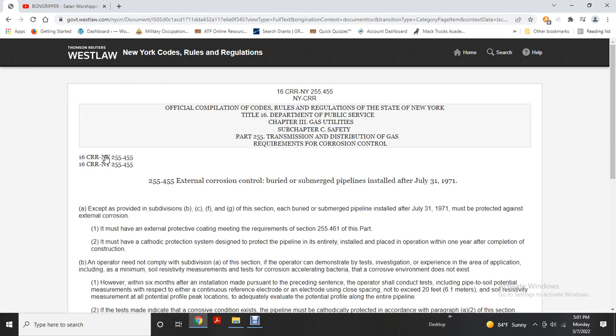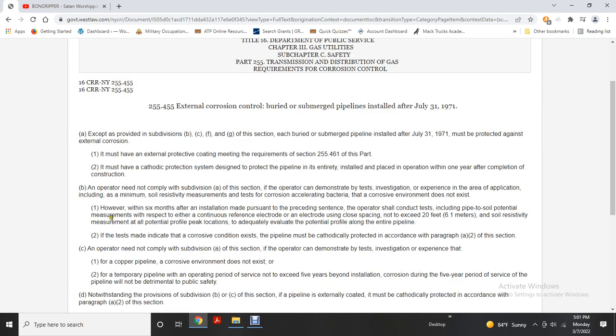External corrosion for buried and submerged pipelines installed after July 31st must comply with subsections B and C. Cathodic protection must be designed to protect the pipeline, with the requirement to be operational within one year after completion of construction. The operator may demonstrate through testing that the soil resistivity and corrosion environment — including bacteria — do not pose a corrosion risk.